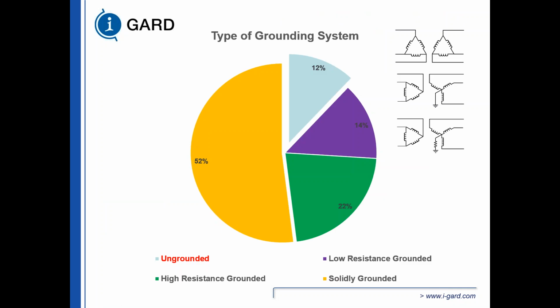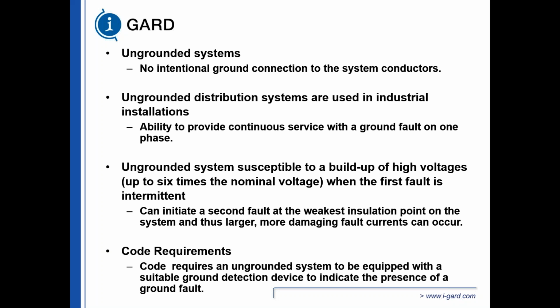So we're going to start with an ungrounded system. 12% of the facilities are ungrounded. Some people believe that ungrounded are really good. Most of the time, they're not really good. So with an ungrounded system, we have no intentional ground connection between the system conductors and ground. So no portion of A, B, or C phase, or L1, L2, and L3 are connected to ground. So it's a completely and totally floating system except for the capacitive loading or the capacitive coupling to ground.